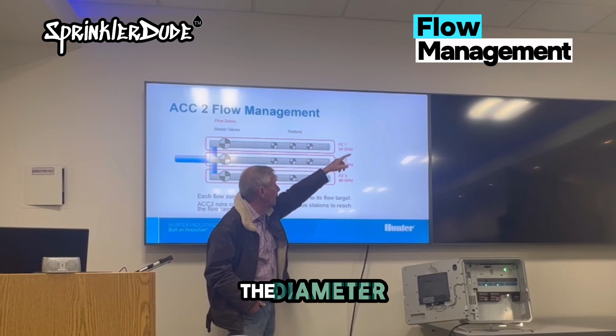Then your flow monitoring kicks in. The flow monitor looks at the flow meter on the piping system. It knows which stations are running and what they should be doing - now it's looking at the real world. Maybe it's doing flow management, or you're just running a lot of stuff at once. It adds up what ought to be happening based on the learned flow and compares it to what's really happening in the field.